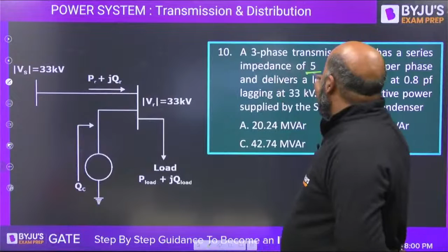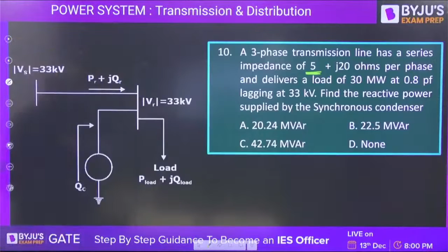This is the real and reactive power requirement of the load, and this is the real and reactive power coming from the source side at the receiving end. The receiving end and sending end voltages are same, 33 kilovolt. Now you cannot apply the shortcut formulas in this question because it is not lossless. Resistance is also there, 5 plus j20, you have to use Z. Here you have to follow the detailed formula.